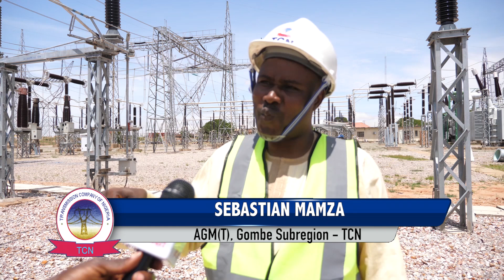The official also gave a highlight of the role the Gombe substation plays in the national electricity grid. From records, this station was established in 1980 with 150 by 2 MVA transformers, and has been expanded from then up to today. We have 540 megawatts that feeds the northeast part of the country. We get our power from Jos to Gombe. From Gombe, it goes to Potiskum 132, then to Biu 132. From Gombe, it goes to Damaturu through 330, and from Gombe it goes to Yola through 330.